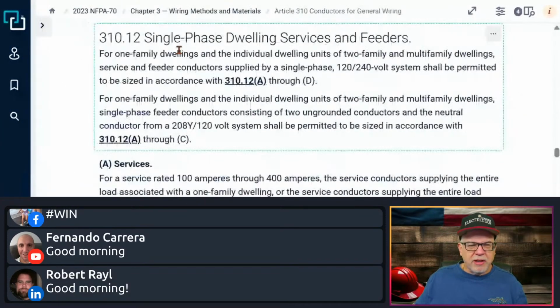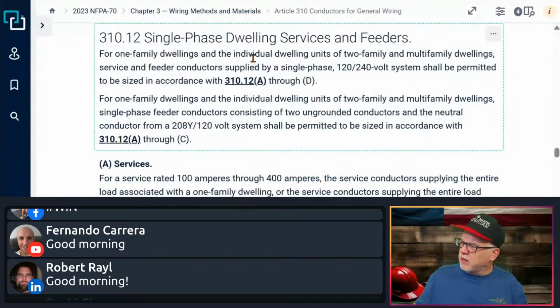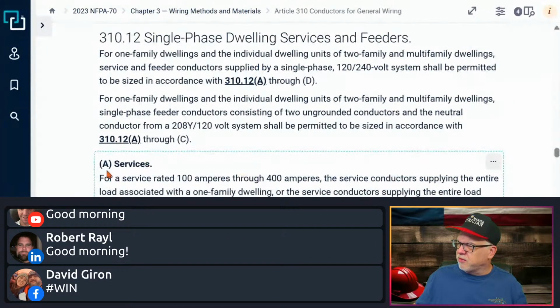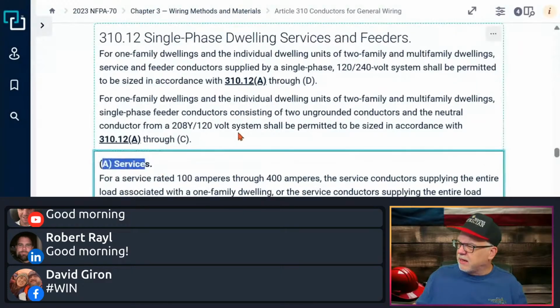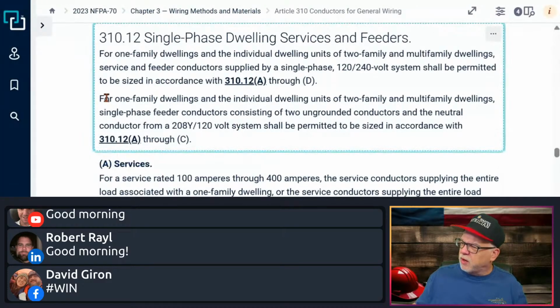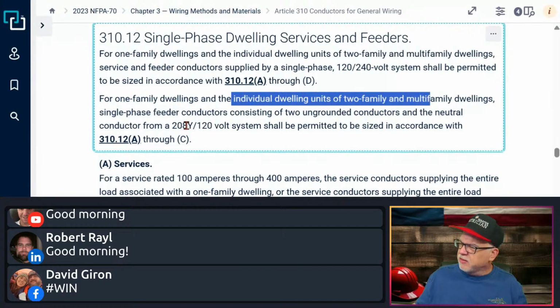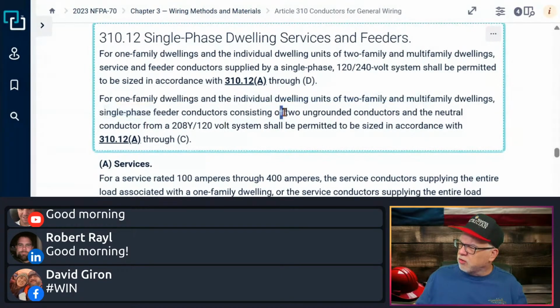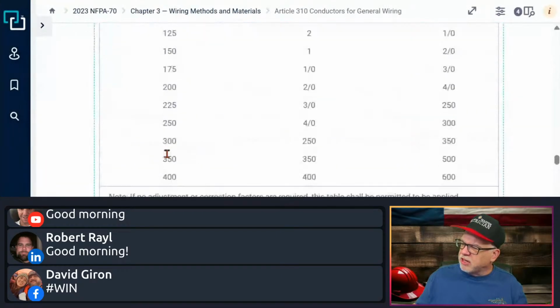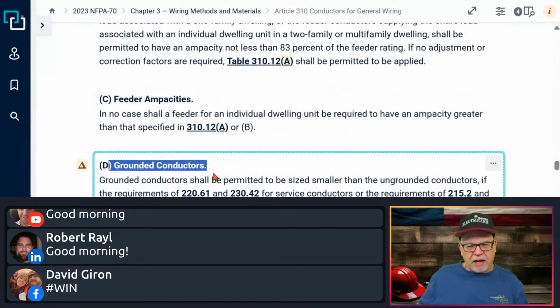All right. So here's 310.12, single-phase dwelling units, and we're talking services. And by the way, it also applies to one-family dwellings and individual dwelling units of two-family and multifamily dwellings, single phase consisting of two ungrounded conductors and a neutral from a 208Y/120 system, which shall be permitted to be sized in accordance with 310.12 A through C. The reason you can't use D is because that's for the grounded conductor.